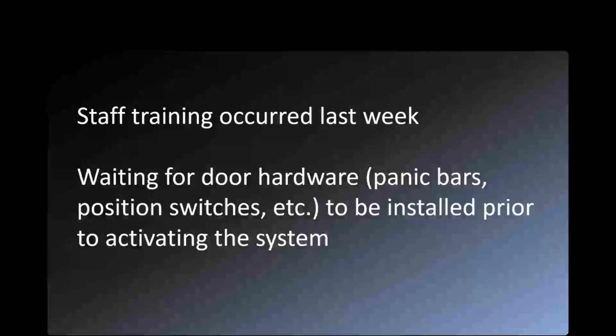The system is in, and staff training has occurred. On these systems, the issue is that once it starts to alarm—once it says it's going to go off—you have a few seconds to say it's a false alarm, please don't go off, because once the system activates it's very expensive to refill the tanks. Also, it won't kill people, but it is a hazard to anyone working in the area—we don't want you breathing stuff you don't need to breathe.